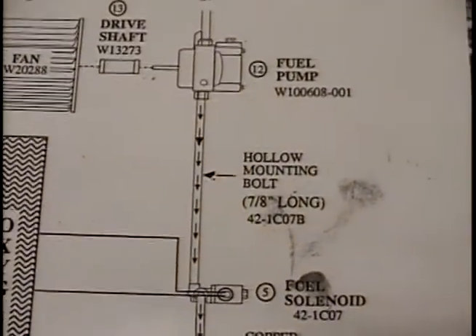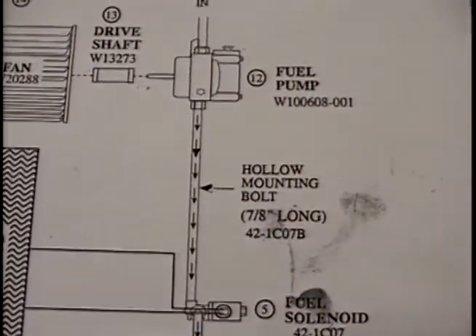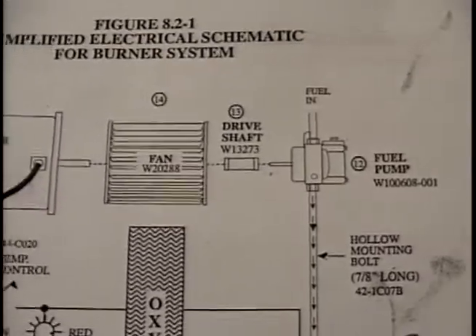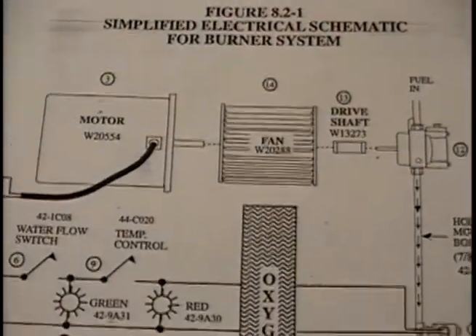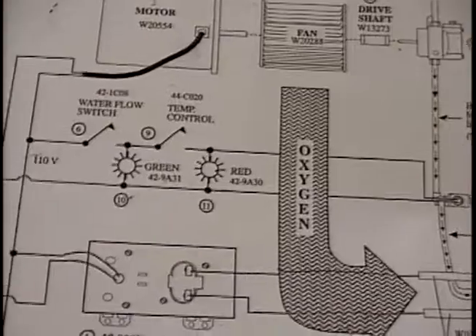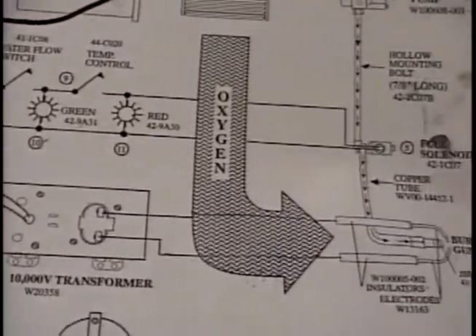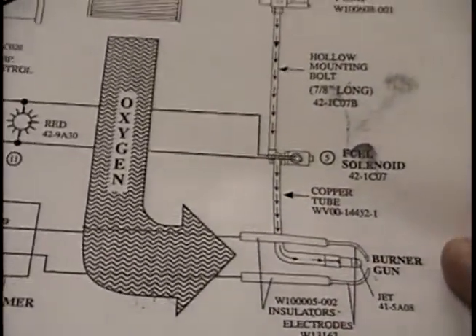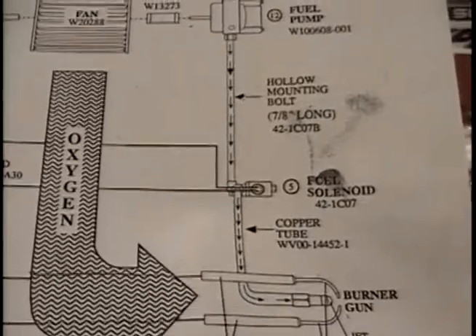Up to now, that's what's happened. We've got the fan running, driving the kerosene fuel pump through a shaft. We have almost everything we need to get a fire started, except we're pushing fuel to the solenoid, and the solenoid says, you can't come here yet, the door's not open. There are 2 switches, 2 components involved in this middle circuit that have to be closed at the same time for the heater to come on.